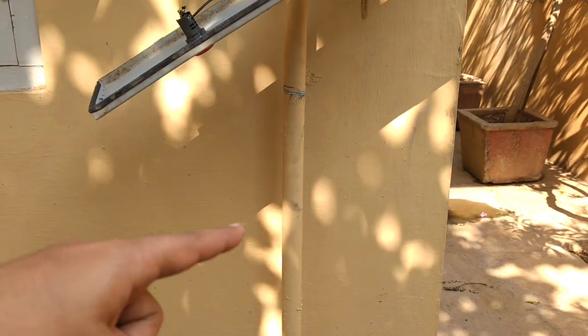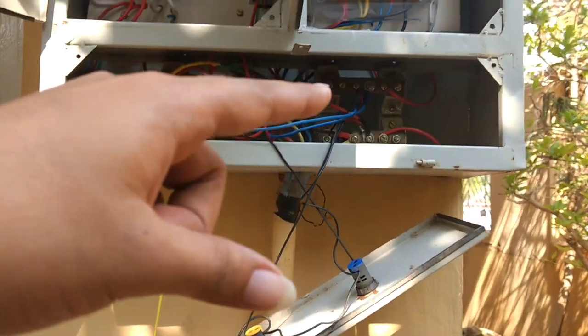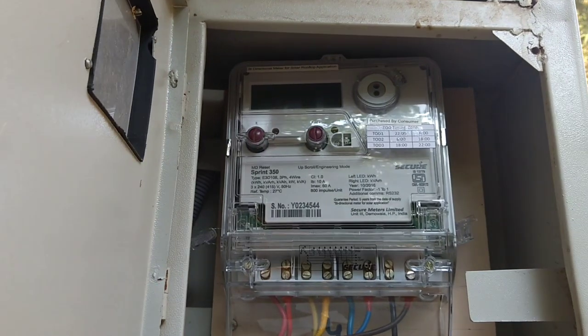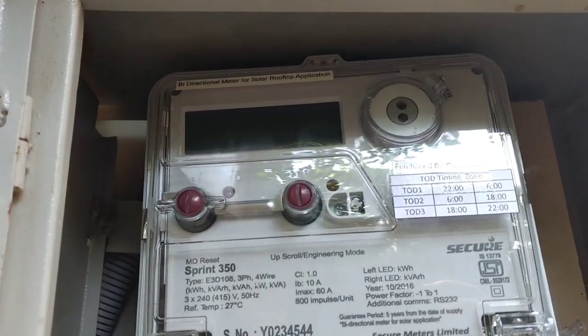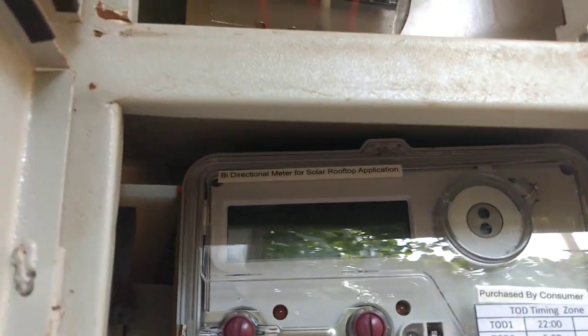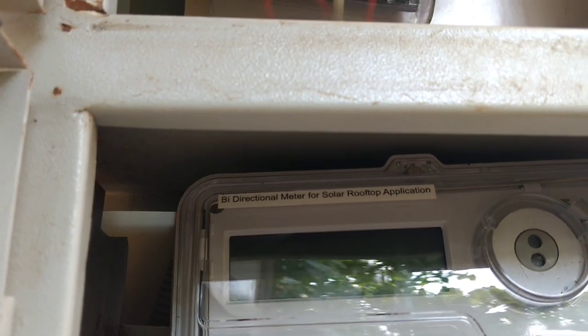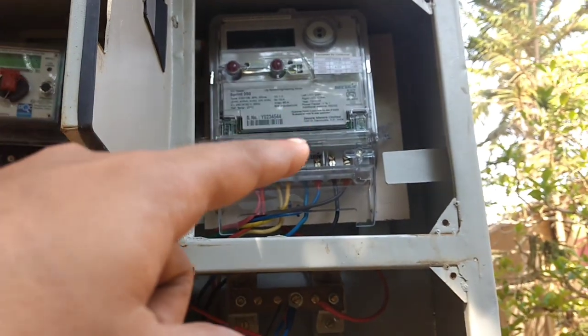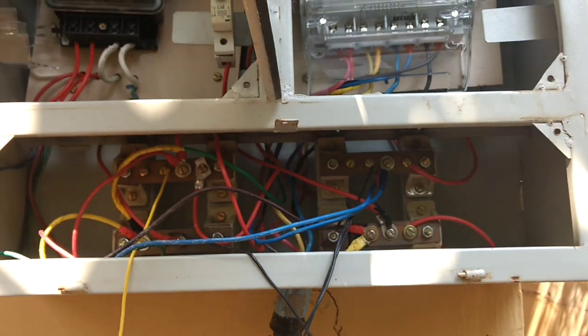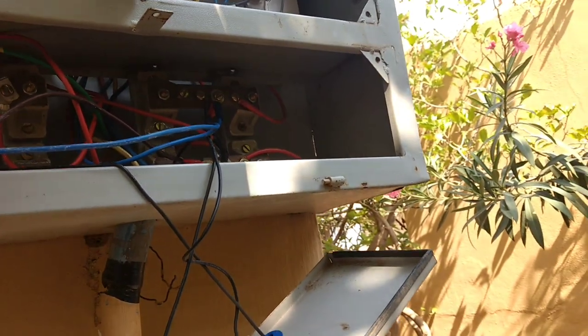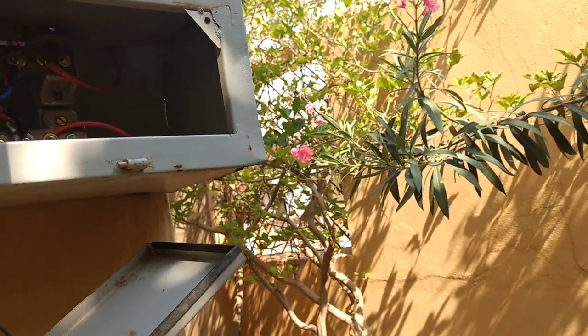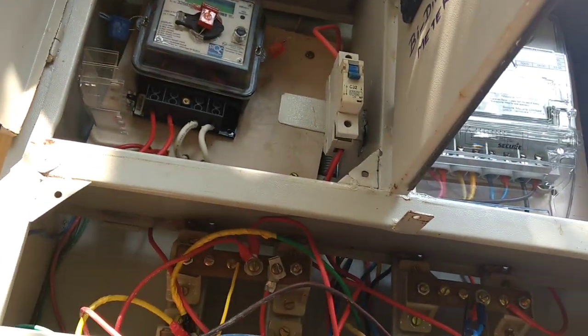You can see the grid pole which is outside the house. From there the four-core cable is coming from underground. This is the pipe which is going inside and it is directly connected to this bi-directional meter, which is especially available in the market. Why is it bi-directional? Because it will show you the import unit and the export unit both. So the output of this meter is connected with this bus bar. I'll explain you why we have done this.